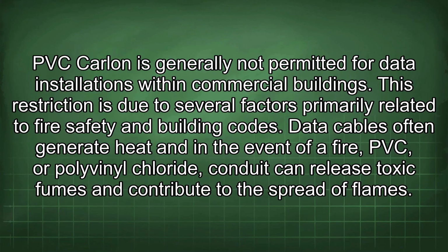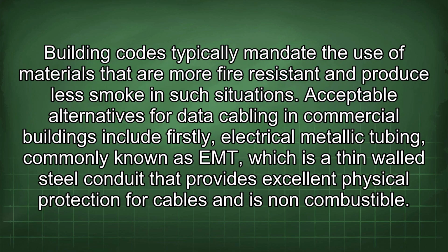PVC Carlon is generally not permitted for data installations within commercial buildings. This restriction is due to several factors primarily related to fire safety and building codes. Data cables often generate heat, and in the event of a fire, PVC, or polyvinyl chloride, conduit can release toxic fumes and contribute to the spread of flames. Building codes typically mandate the use of materials that are more fire-resistant and produce less smoke in such situations.